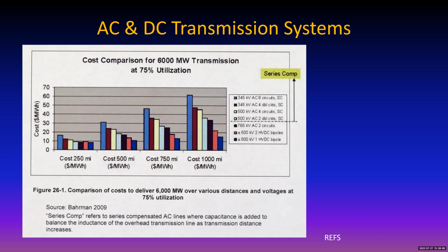And it's very interesting to see just 2 big wires and a ground wire along the top rather than 3 wires in a typical 3-phase AC circuit. But look at the cost. The least expensive for 1,000 miles is an 800,000 volt high voltage DC, whereas if you want to do that with 345,000 volts AC with 8 circuits, that's the big, tall blue one.